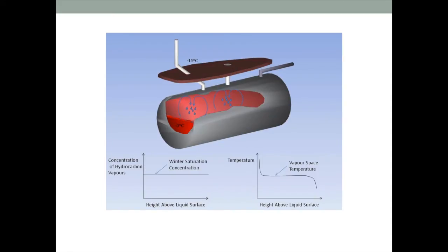What we found was that that wasn't the case. In both above-ground and below-ground tanks, when you have a liquid that's warm relative to the ambient air, the ambient air coming in and contacting the liquid surface will warm up and expand, causing vapor growth in the tank, causing mixing to take place, and you tend to get well-mixed conditions. If the product is cold relative to the ambient air, it would tend to promote stratification — a cold layer towards the liquid surface that is denser than the warmer air above it, which is typical of conditions in the lower 48 states. But if you try to do a mass balance on the system, the API assumption is that you come to this equilibrium condition without causing any emissions, and that emissions only occur when you displace that equilibrium mixture during a filling event.